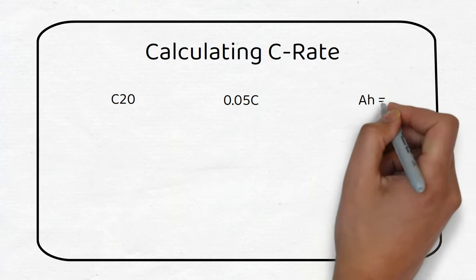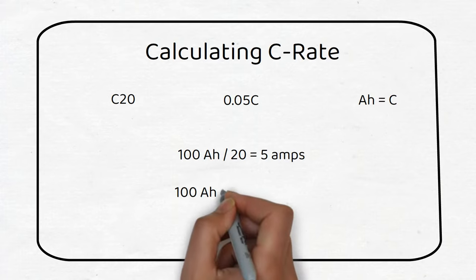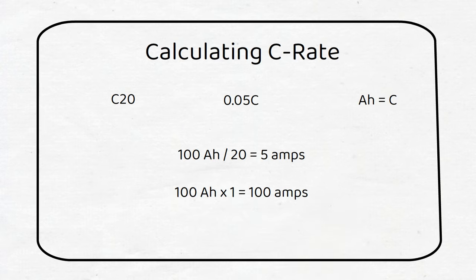The battery capacity and amp hours is used as C. Let's take an example for a lead acid battery. If you have a battery rated for C20, you divide the amp hours of the battery by 20. For example we have a battery of 100 amp hours with a C-Rate of 20. Then we can charge and discharge the battery at 5 amps. If we use another example for lithium at 1C discharge, we multiply the battery capacity by 1. We can now charge and discharge the battery at 100 amps.